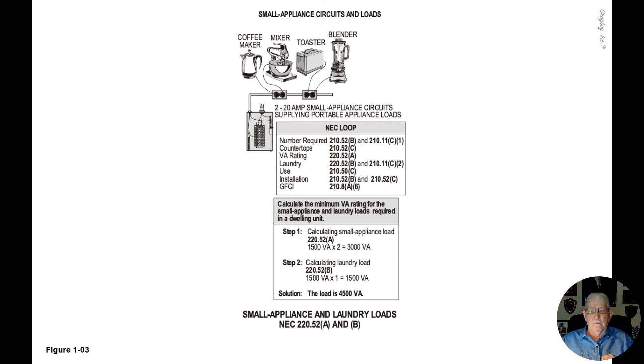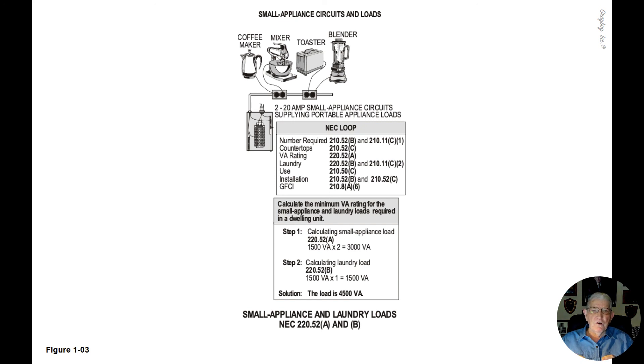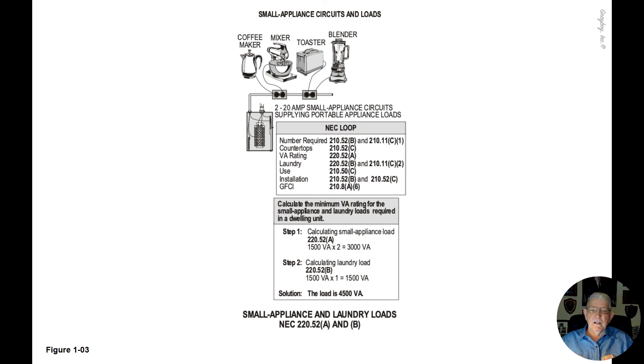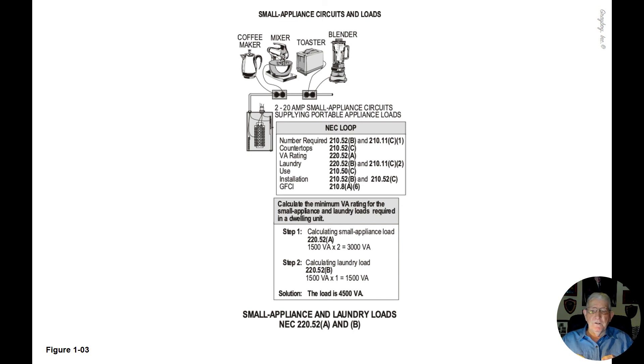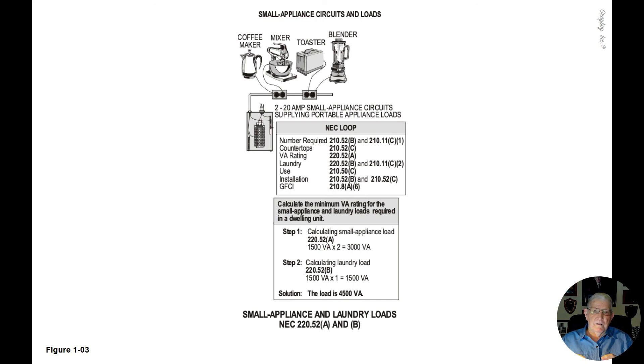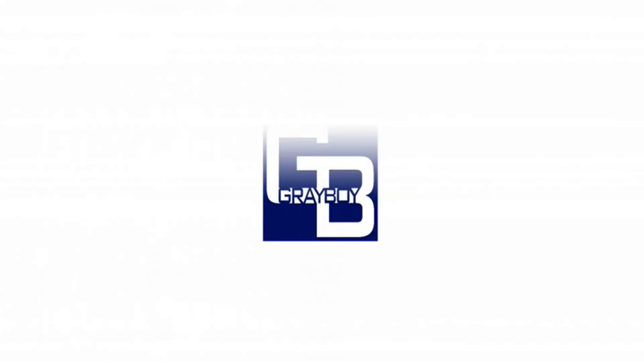In the final solution, when you add 3,000 to 1,500 VA, we come up with 4,500 VA for the small appliance circuits for the kitchen, pantry, dining room and laundry room, in accordance with NEC 220.52A and B. That's what figure 1-3 is illustrating, the procedure for finding the load for the small appliance circuits in VA.